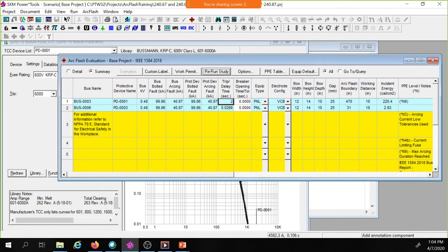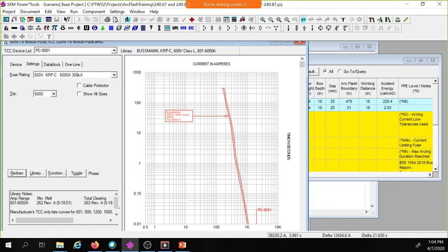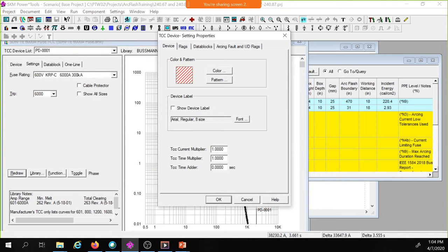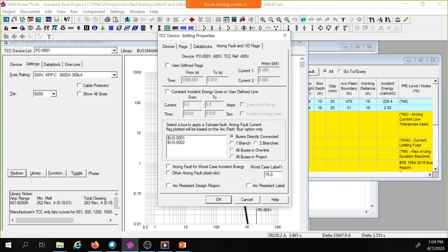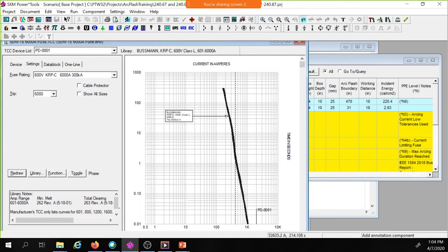So 40.87. Let's take a look at what 40.87 is. I'm going to add that in here: 40,870 amps. There's my 40,870 amps. Look at my clearing time: it's over 2 seconds, somewhere between 2 and 3 seconds.